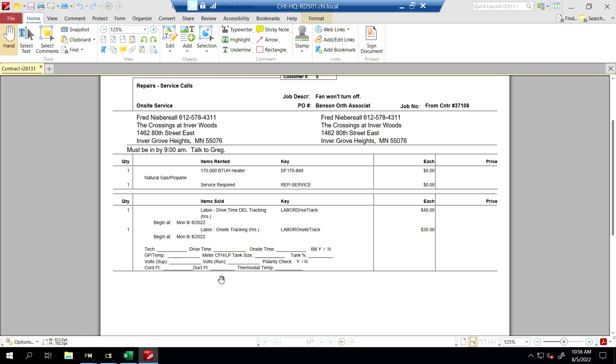Duct. How many feet of duct do they have? Really, most heaters are 25 and 25 feet. Some can do 50 feet. So put down - and they could have 300 feet of duct on here. Write that down so we can catch that and reduce that number before there are future service calls.